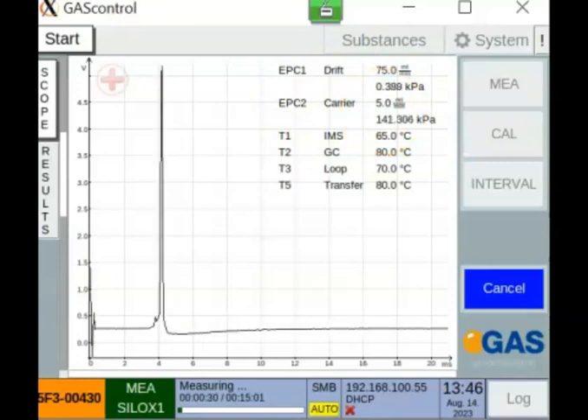The recording of the measurement starts, and when we are next to the instrument, we will hear the switching of the 6-port valve around 1 minute after starting the measurement. We inject and the measurement can make its progress. It is injected now, and we should soon see some progress on the start screen here in the scope view.